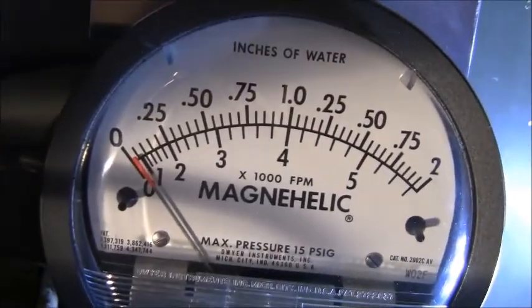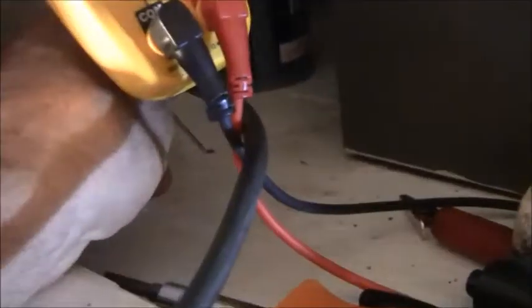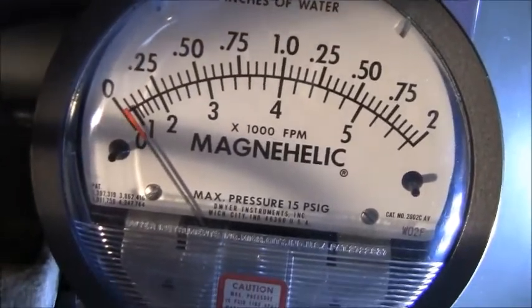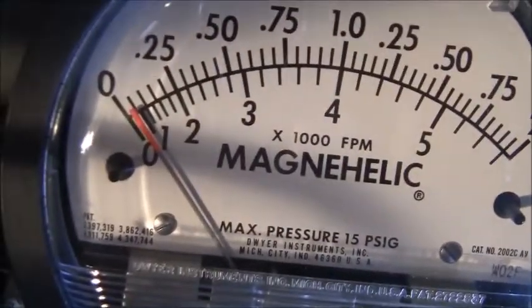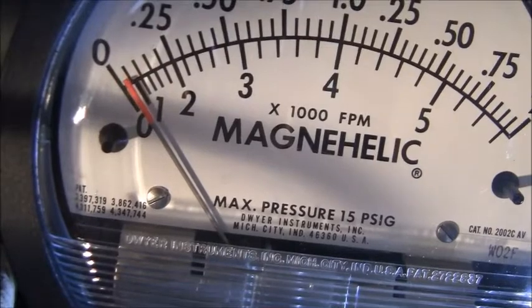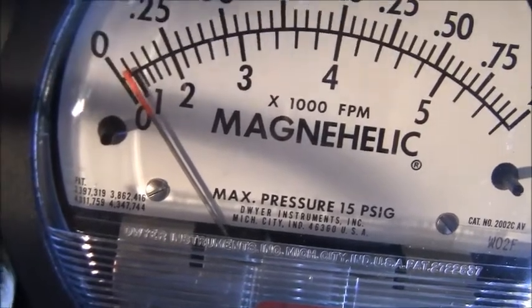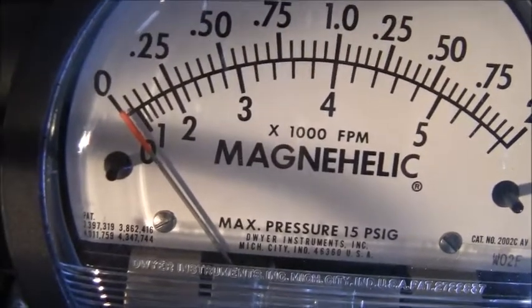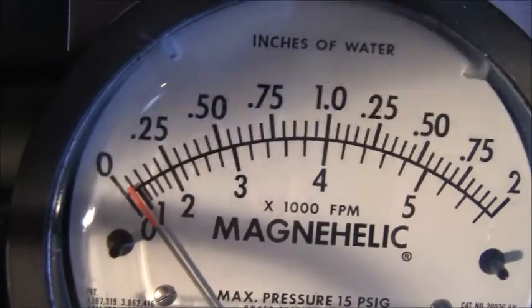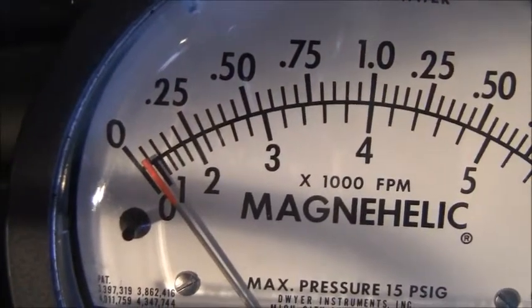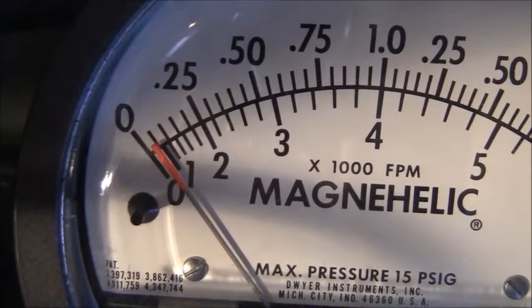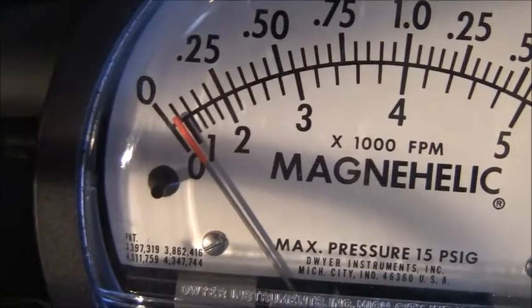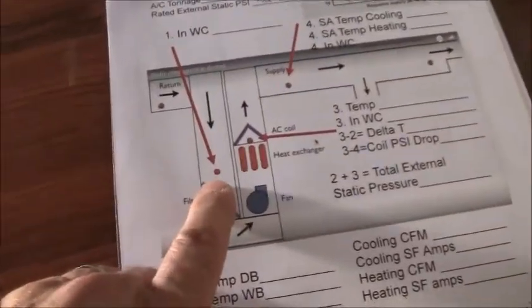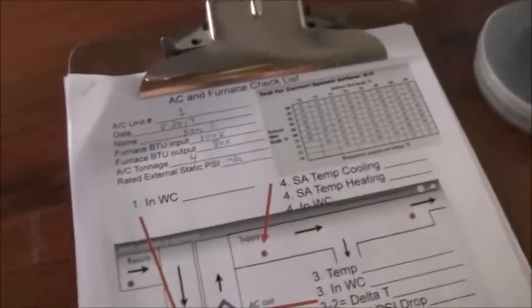Now, watch the gauge. I'm pulling it out, and then I'm going to put it back in, and you'll see the gauge move as I put it back in. Very, very slightly. Pull it out, put it back in. See how the gauge moves just a very small amount. I'm at the very bottom edge of the scale. Looking at those lines, to the left of 0.25 it's 0.20, 0.15, 0.10, so it's 0.05. So pre-filter is 0.05, and that is the number we are going to populate for this point, 0.05 inches of water column.